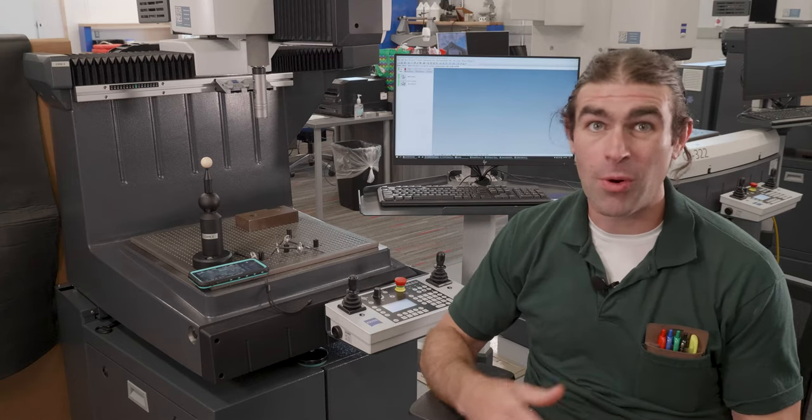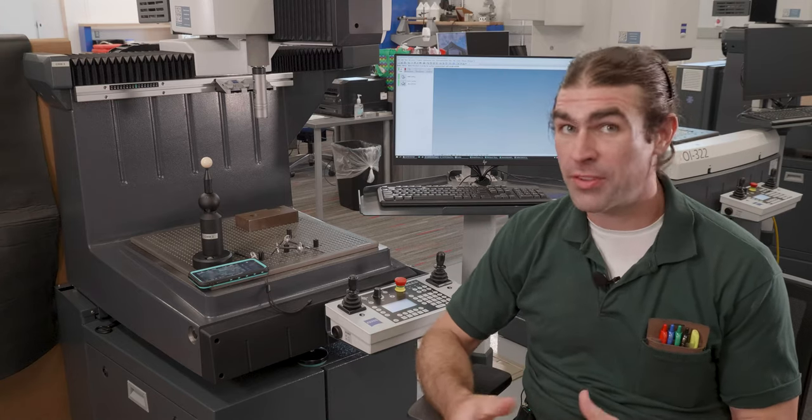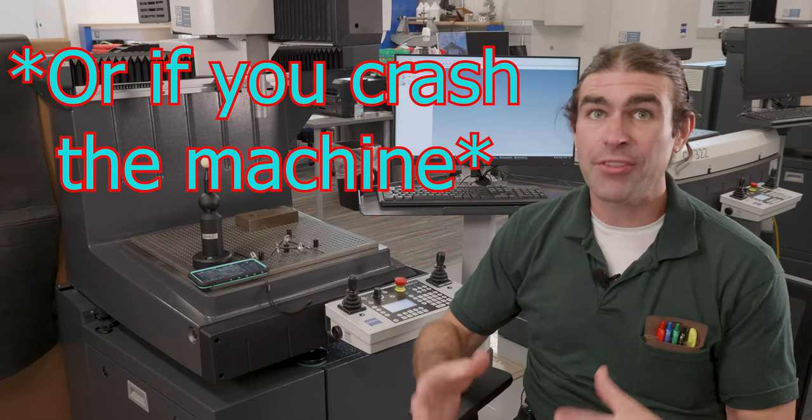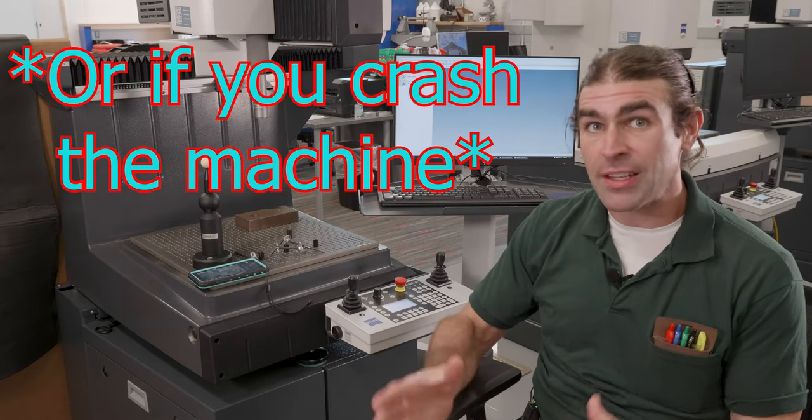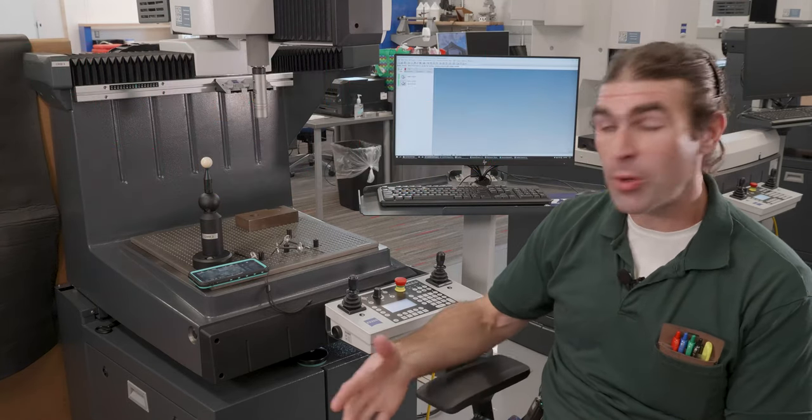You should re-qualify probes maybe once a week or once a shift if you're using the machine a lot. But you have to do it at least once the first time.